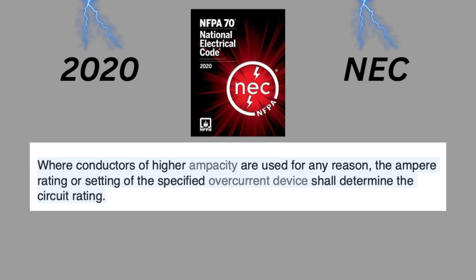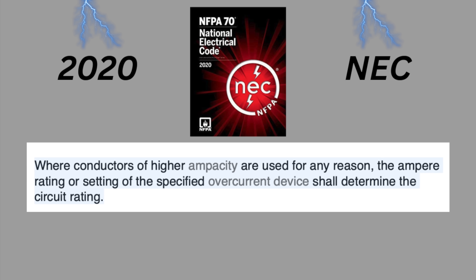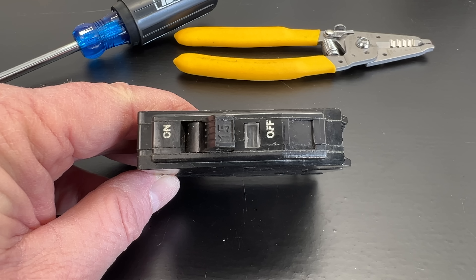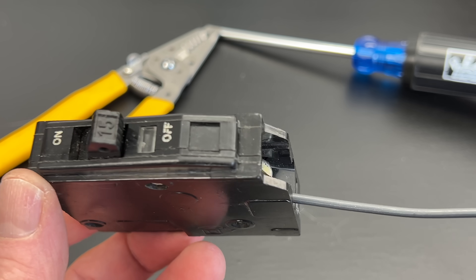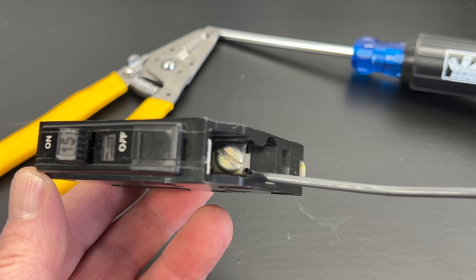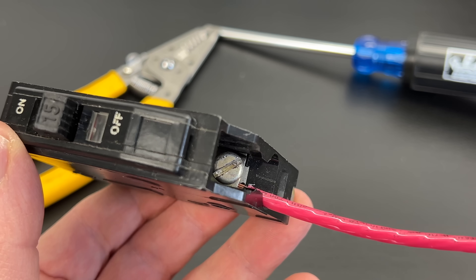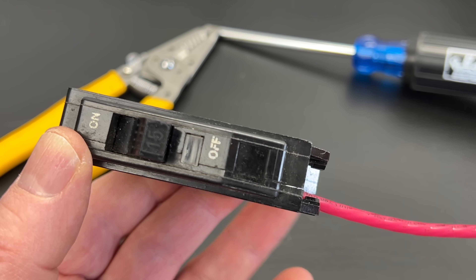It goes on to say, 'Where conductors of higher ampacity are used for any reason, the ampere rating or setting of the specified overcurrent device shall determine the circuit rating.' What that means is that a circuit's amp rating is based on the rating of the circuit breaker rather than the size of the wire. For example, it's okay to run 12-gauge wire connected to a 15-amp circuit breaker. In fact, you can run 10-gauge wire with a 15-amp circuit breaker, but the circuit ampacity will remain 15 amps.